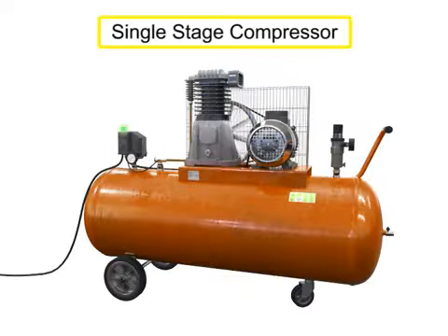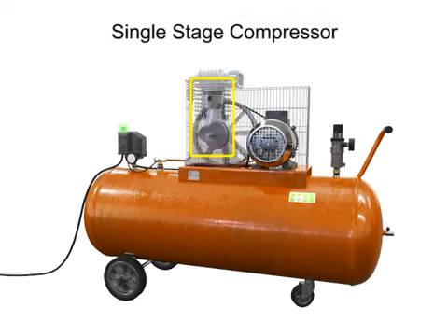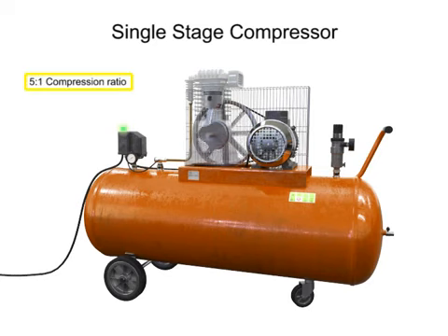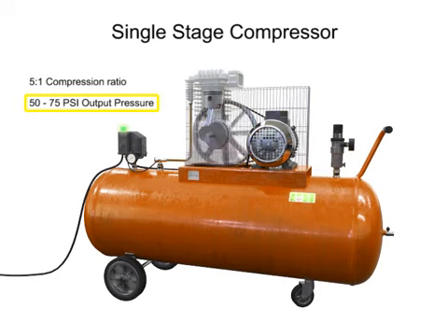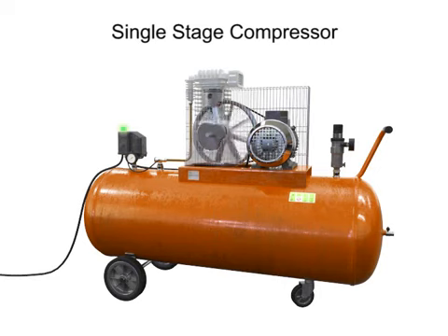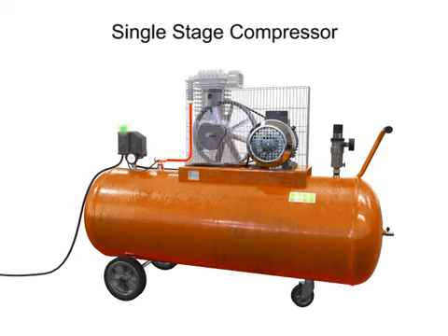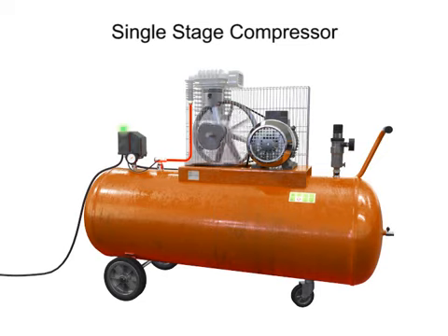This is a single-stage compressor. It has only one piston and cylinder, and compresses the air in only one stage. A single-stage compressor typically has a compression ratio of 5 to 1, with an output pressure of about 50 to 75 PSI. As air is compressed, it becomes increasingly hot. If the air becomes too hot, not only is the compression cycle less efficient, but there is the hazard of an explosion if any hydrocarbon material, such as oil or lubricant, comes into contact with the overheated air.